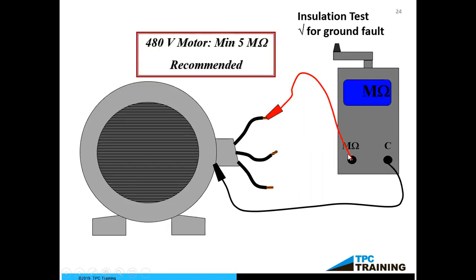But we're going to take the red lead, the meg ohm lead, and it's going to go to T1. We're going to take the earth lead or the common lead, and it's going to go to the frame of the motor. When we put this on the frame of the motor, we'd like to put it in a place where there's no paint. We want a real good connection to the frame of that motor. And in this case, we would start turning the crank and see what it gave us for a reading.